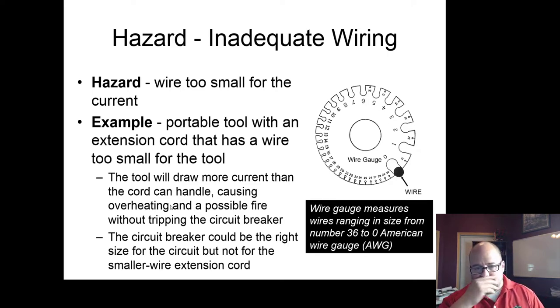But as you see on the screen, the gauge of the wire — here's a 12-2 Romex — dictates the maximum amperage that can be drawn through it. So again, this is a 12; a 12 gauge is designed for 20 amps, and a 14 gauge is designed for 15 amps. So the greater the amps, the greater the size of the cord.